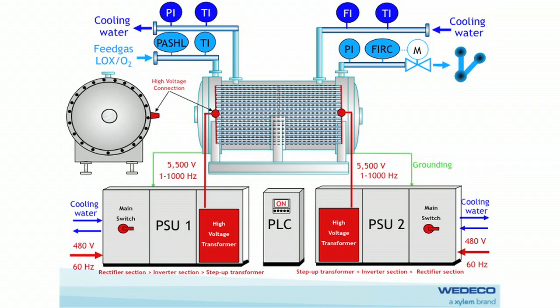As you can see, there's the placing of the electrodes into the outer shell. Tedious job. There's then a better graphic of how the whole process works. You can see the outer shell of the generator with all of the tubes inside. We place the tubes into the whole system. We hook it up to the high voltage current. Let's say about 5,000 volts onto the thing, close it up.